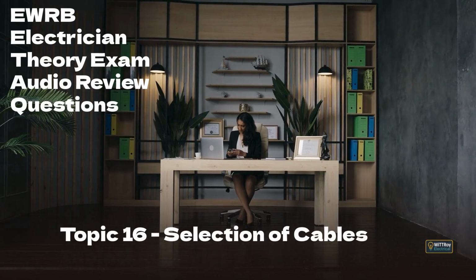Pause. 5, 4, 3, 2, 1, 0. Correct answer is option B. Grouping and insulation trap heat. The cable will run hotter, so you must apply correction factors and may need a larger conductor size to carry the same design load safely.